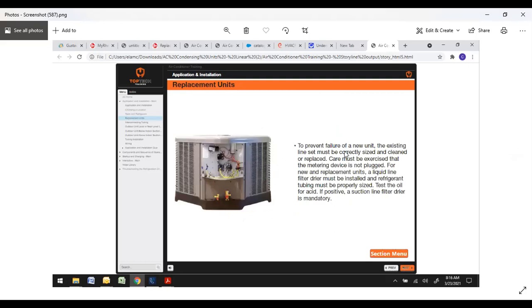Replacement units. To prevent failure of a new unit, the existing line set must be correctly sized and cleaned or replaced. That's imperative. We have guys all the time that try to use existing line sets. They must be the correct size or it will affect operation and your refrigerant pressures and can cause almost immediate issues. Care must be exercised that the metering device does not get plugged. So if there's any kind of debris, dirt, it will clog up your TXV or piston if you're using a piston.